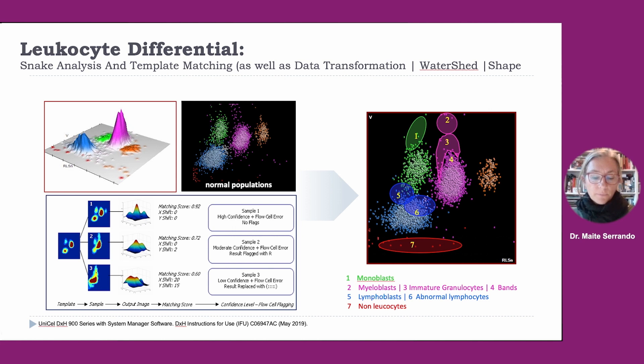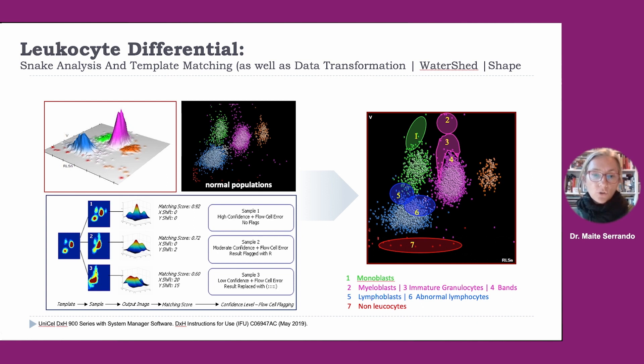These are two complementary features that allow the machine to identify abnormal cells. The snake analysis defines boundaries between populations, enabling identification of abnormal cells. Template matching is used to identify the presence of abnormal cells — the scattergrams are compared to a normal pattern of cell distribution, obtaining a matching score with three levels of confidence: high, medium, and low. This analysis enables the DXH 900 analyzer to flag samples, identifying groups of abnormal cells.